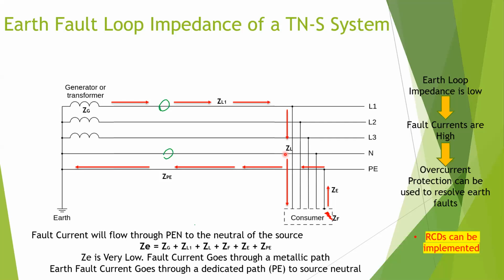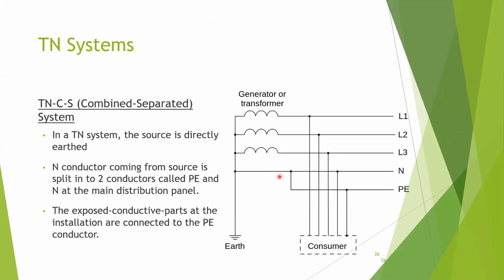It is in dedicated transformer locations. That means high-rise buildings and all. So there are a lot of distribution panels. So from the main distribution panel, we are dividing this neutral into two wires like this. So assume in here we have the main distribution panel. So we are connecting another wire to this neutral, and we are creating 5 lines from that point onwards.